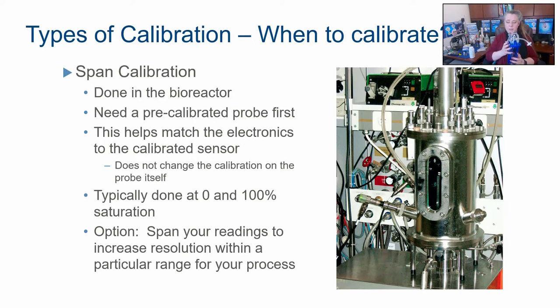Now I'm going to do my span. So I hook up my cable from my bioreactor to my probe. This is important that you hook it up because you're also going to be calibrating the cable and any of the electronics and the impedance on that. All of that gets factored in now. It's called a span calibration and it's done in the bioreactor. So I've got liquid in here.